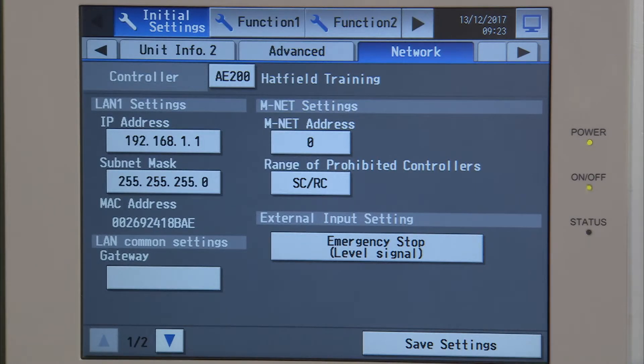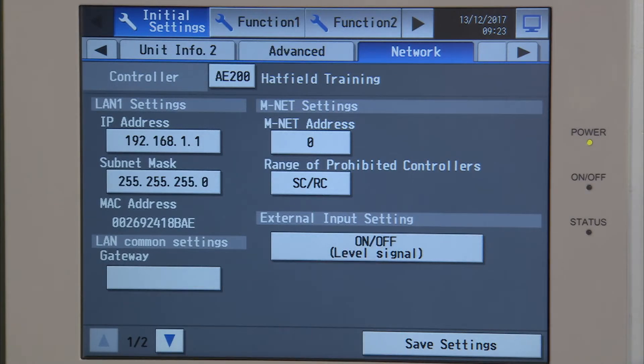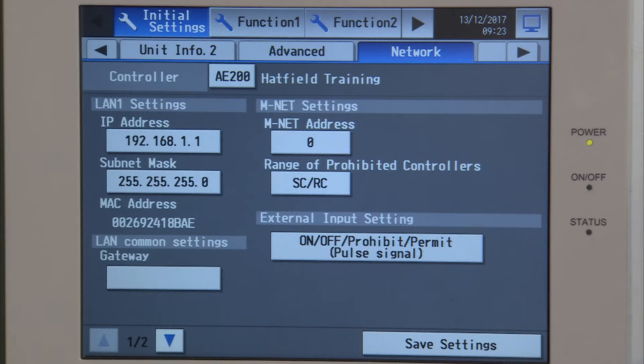When the contacts are opened again, you will be able to switch the air conditioning back on, but it will not come back on automatically. Click on it again and it now becomes an on/off: when you make the contact it switches all the air conditioning on, and when you open the contact it switches all the air conditioning off. There's another option for a pulse signal, but in the UK we don't use pulse signal.